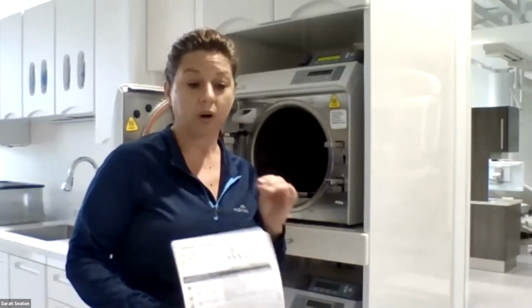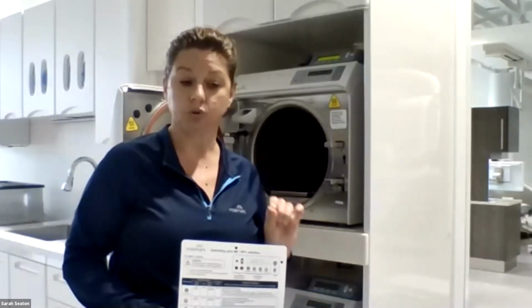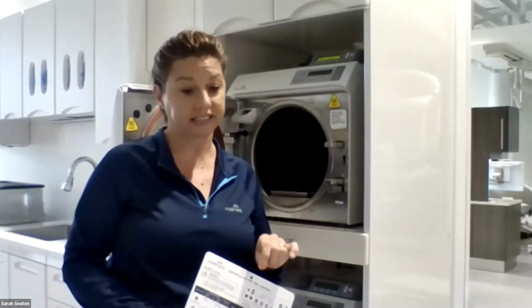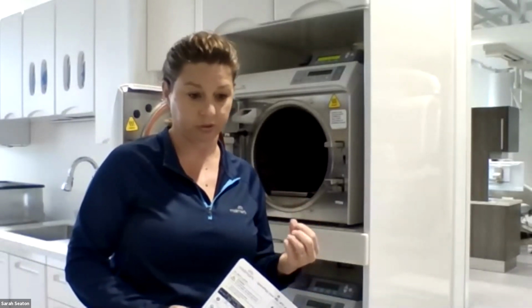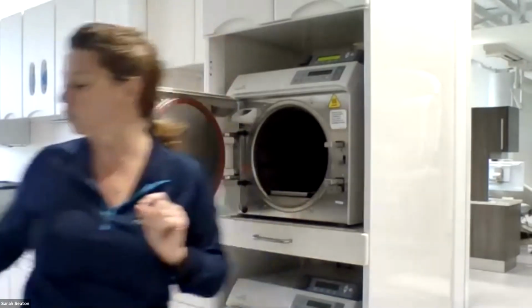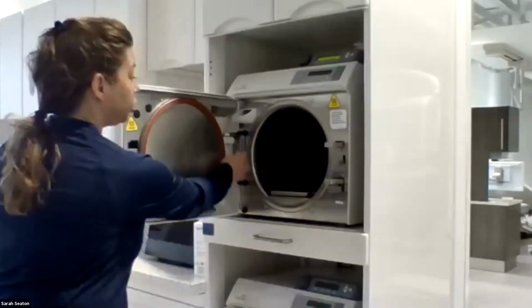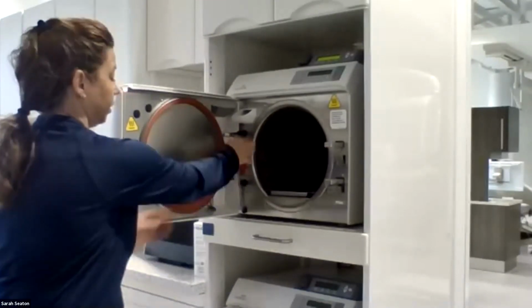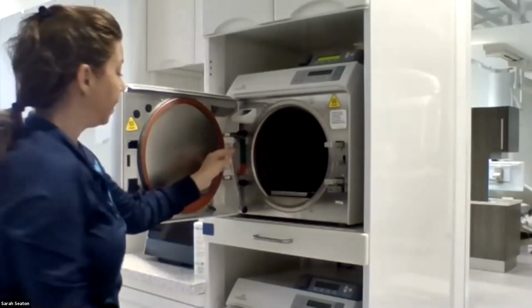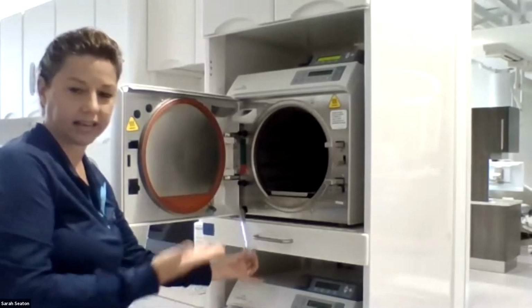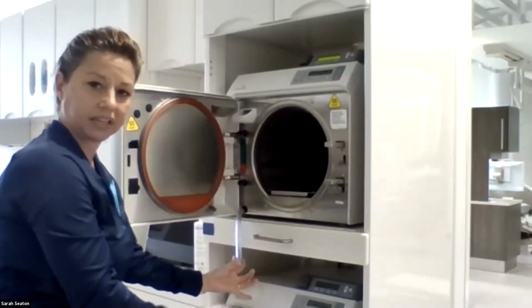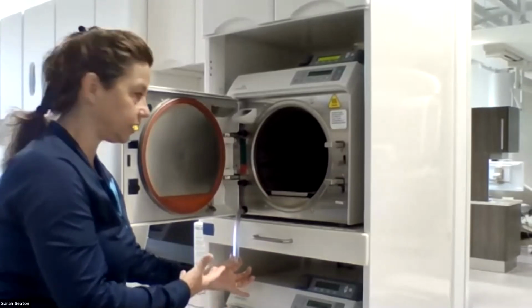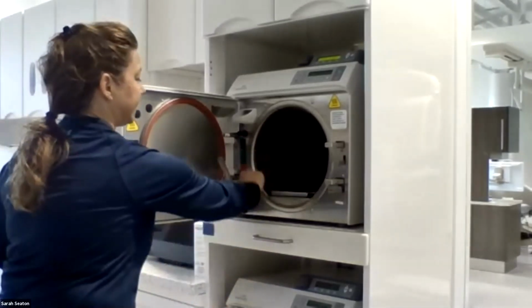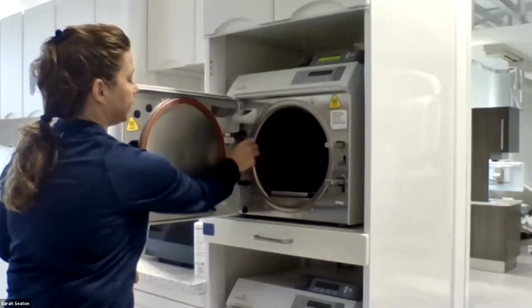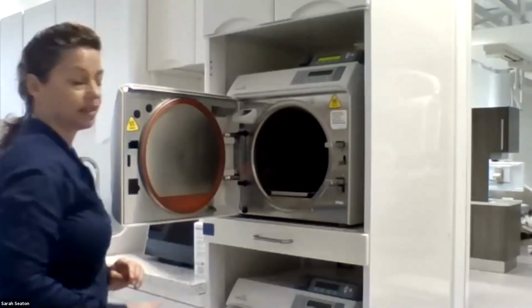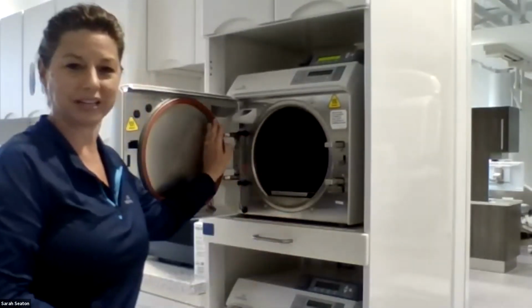So when you're doing that, you're going to drain the reservoir and refill it with clean distilled water, as well as wipe your surfaces. To drain your reservoir, you'll want to unclip your hose, and then of course just point it down so that gravity drains the water out of your sterilizer reservoir. If you see this indicating line, this tube is also used as a water level indicator for inside your reservoir.